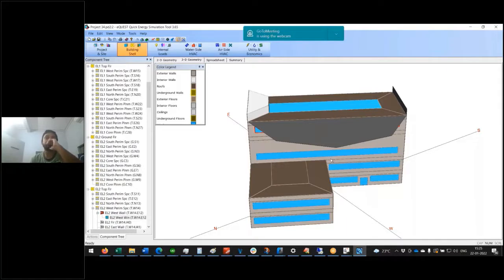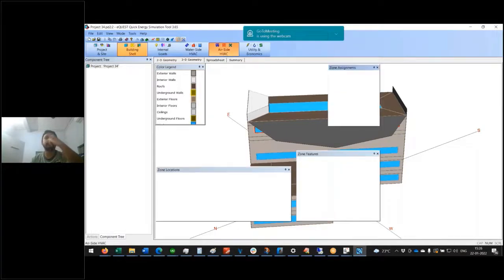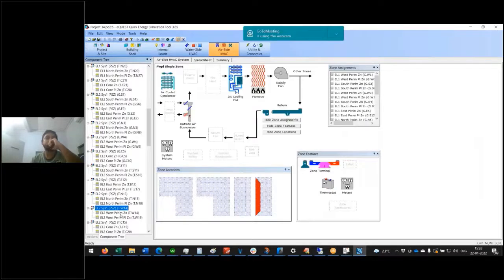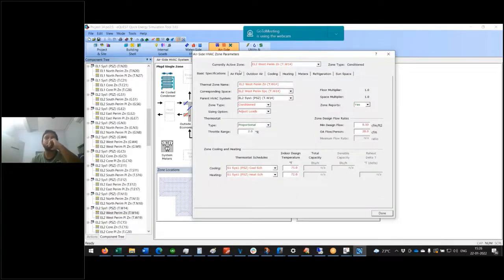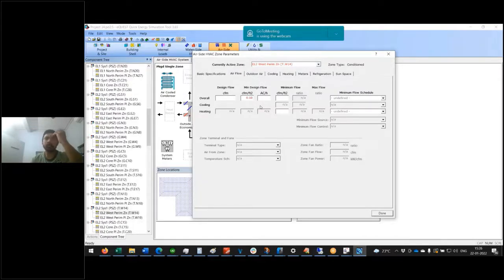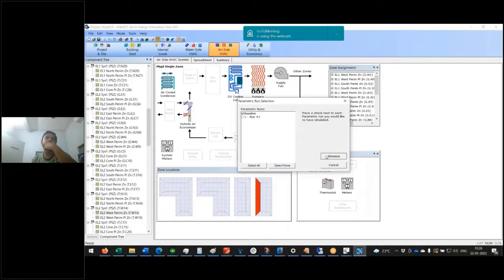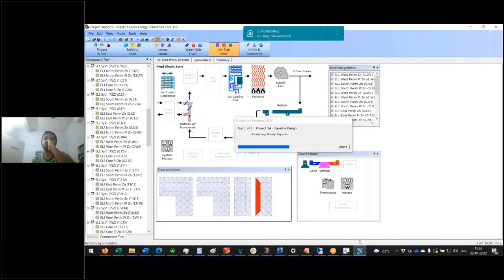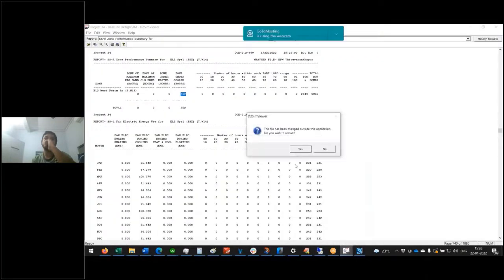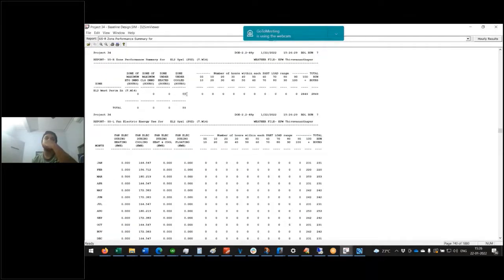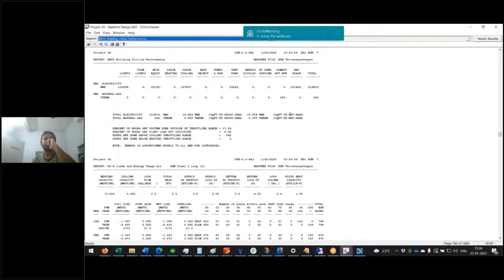One of the things that you could look out for is, as I said, this one, airflow. You could actually increase it to about 1.5. Let's say if I put it as 1.5, it should ideally satisfy. Yeah, as you can see, the throttling range has come down, and it is at 492. So probably a couple of zones would be left.